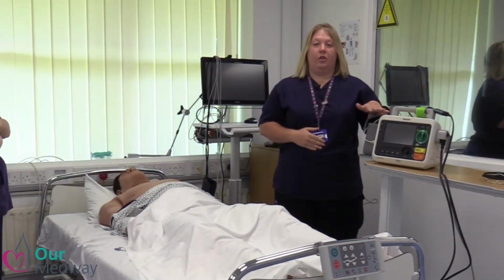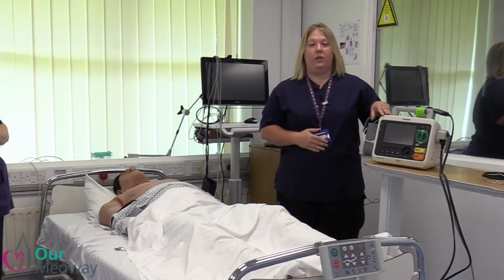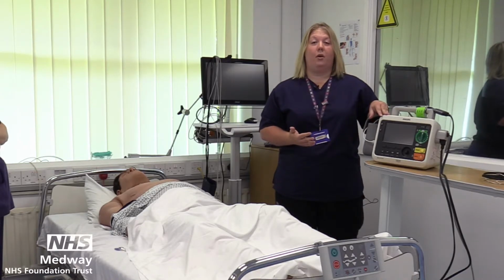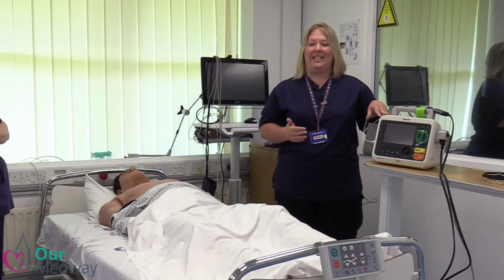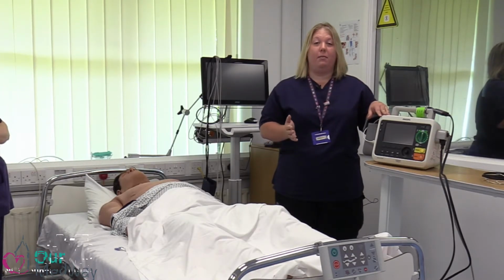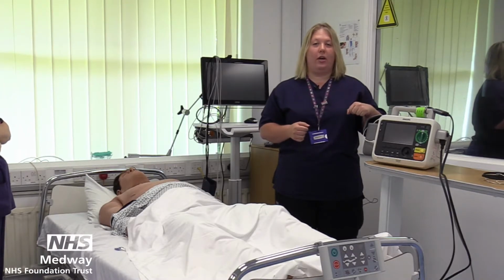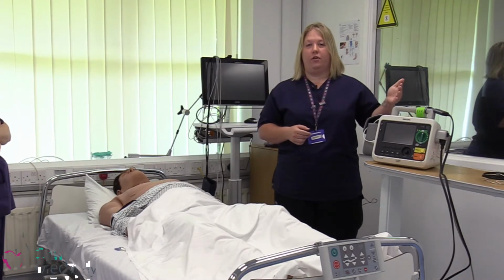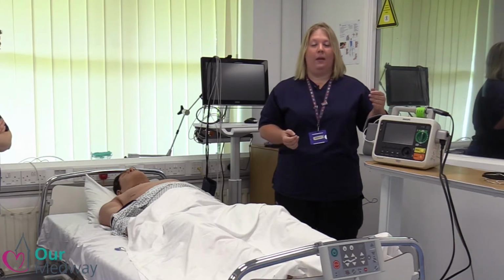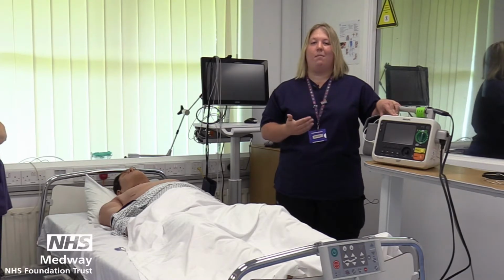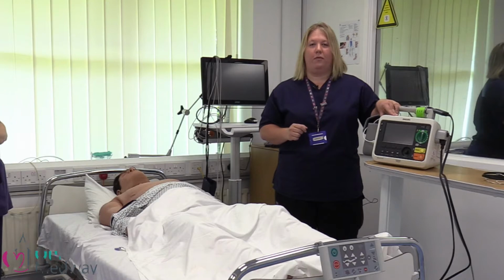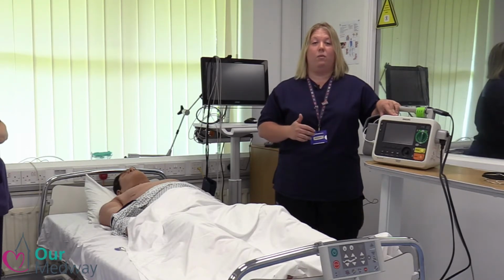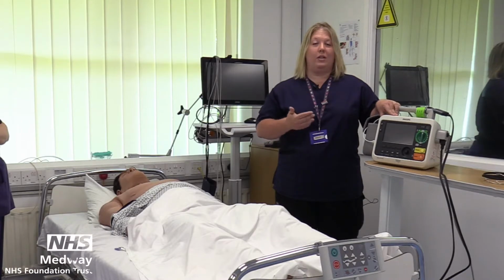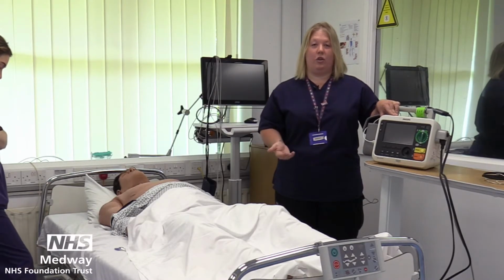So now I would like to show you our manual defibrillator in use. This type of defibrillator has two modes of delivering a shock during cardiac arrest. So you can use it in an AED mode, that's an automated mode, similar to the smaller AED that I showed you earlier, where you turn the machine on and you follow the instructions, and that's absolutely acceptable to do. The other mode you can use is a manual mode, and that's why we often refer to this as our manual defibrillator, and I will show you both methods of delivering a shock. In reality, what I want you to do is deliver the shock in the mode that you are most comfortable with and the one that you have been trained to do.